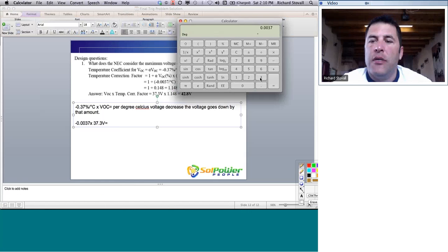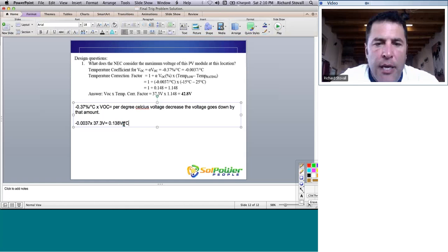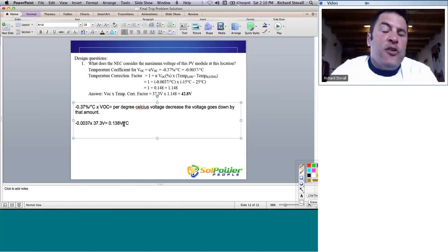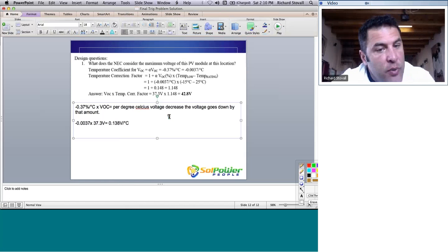0.0037 times 37.3. We get 0.138. So our absolute value of voltage change for this particular device is 0.138. So we're losing 0.138 volts per degree Celsius. Okay? Then, if we want to determine how much voltage increase we'll get, it's a matter of multiplying the number of degrees Celsius away from standard test conditions we are.